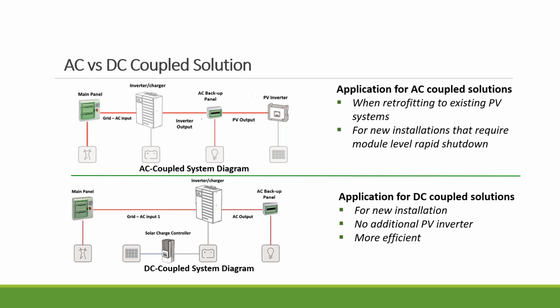Now we're going to go to the inverter section, on basically how to integrate the energy storage to your existing or new PV array. There are two types of configuration when you design the systems. One's called AC coupled, and the other is a DC coupled solution. In an AC coupled solution, you already have a PV inverter there. It connects to the solar panel, and then you have the hybrid inverter, or you call it inverter charger, that is connected to the PV inverter as well as to the main panel. It also connects to the battery.